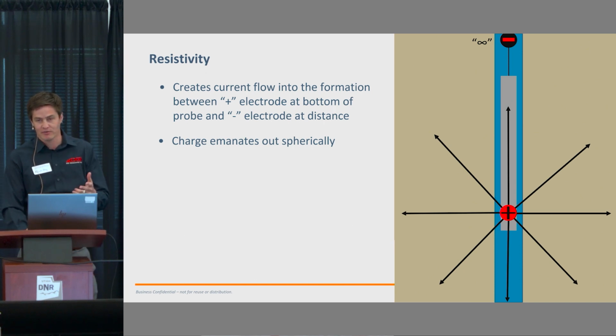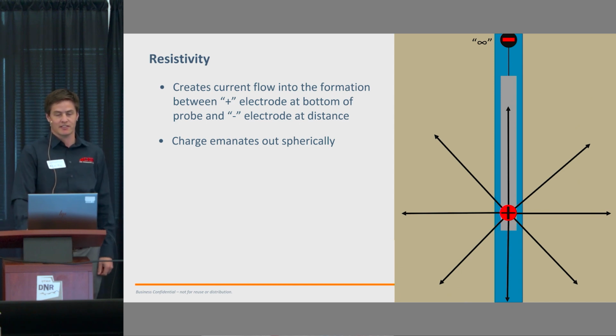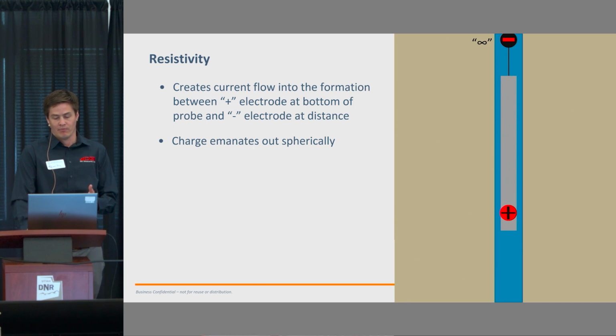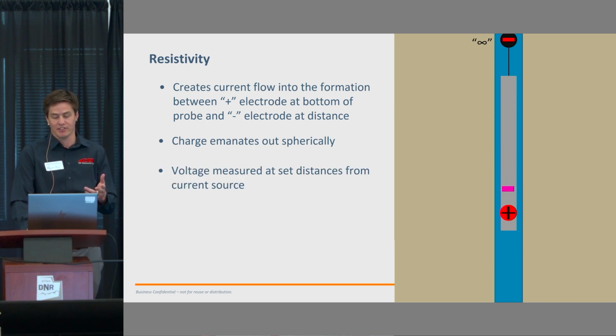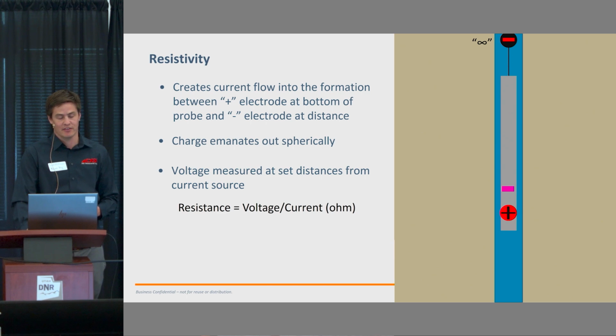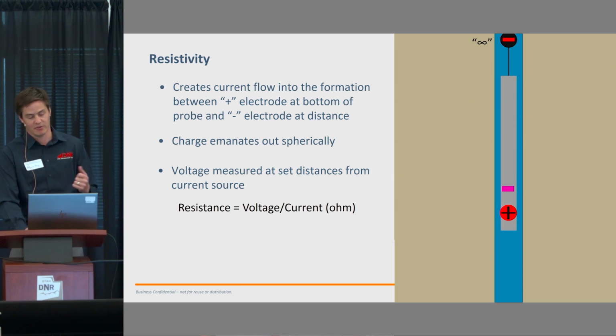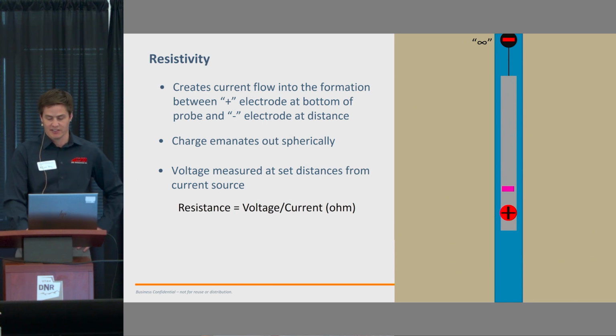So how do we measure resistivity? Well, first we measure resistance just by measuring that voltage. You put a voltmeter on the probe at a certain distance from the electrode, and using basic Ohm's law, resistance is voltage over current. We control the current because we're hooking it up to our generator powering it, and we measure the voltage, do the division, and you get resistance.